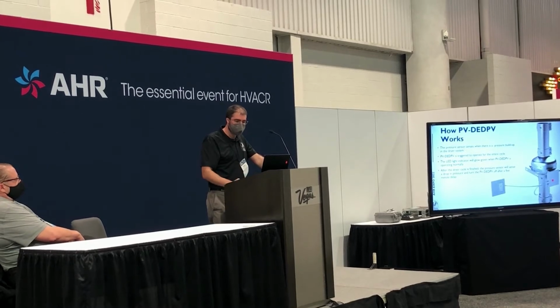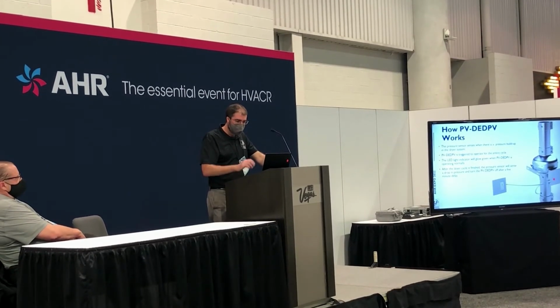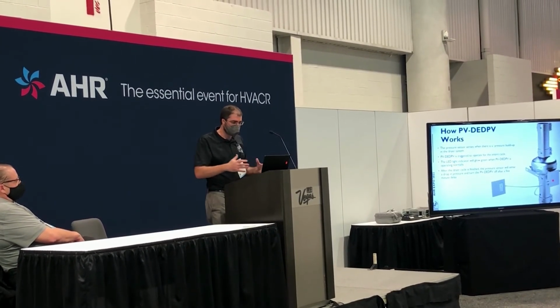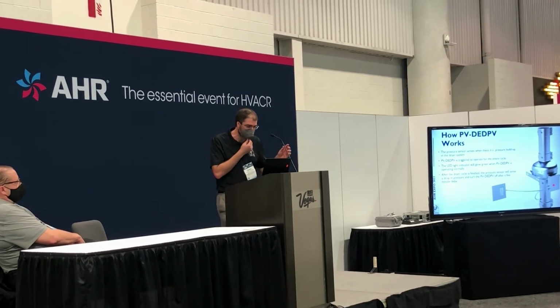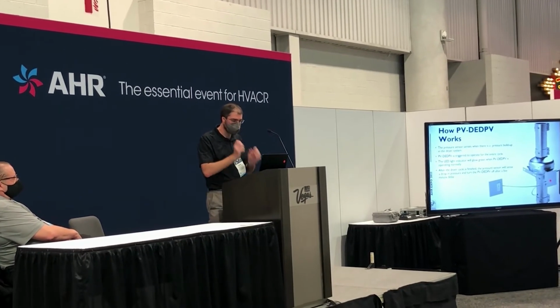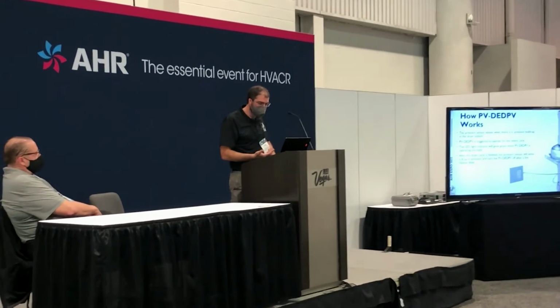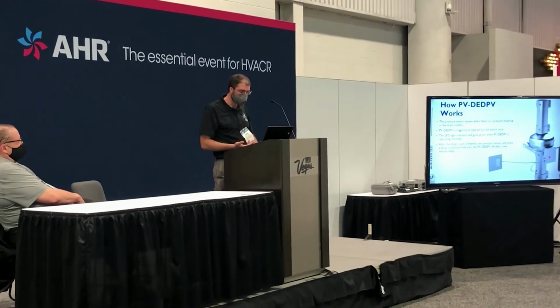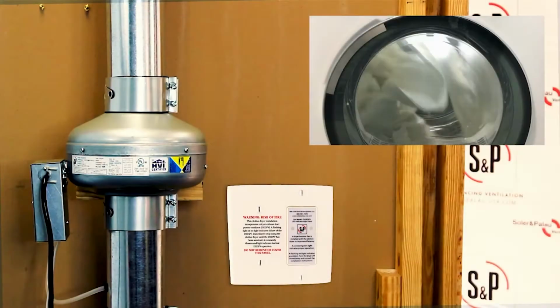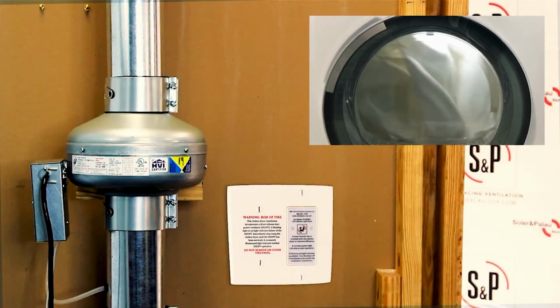Upon sensing pressure, the PV-DEDPV is triggered to operate throughout the entire drying cycle. When the drying cycle is over, the PV-DEDPV will run for a delay of 5 minutes to provide a cool down period, which helps prevent flash fires in the duct system relating to high temperatures and low air velocities that sometimes can occur soon after the dryer turns off.